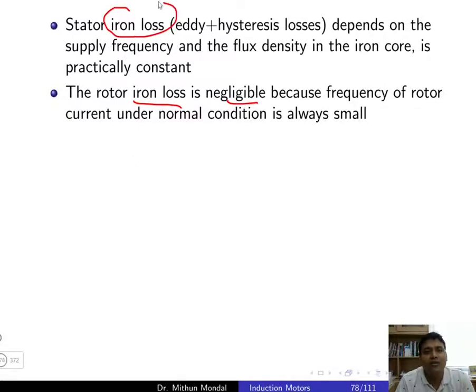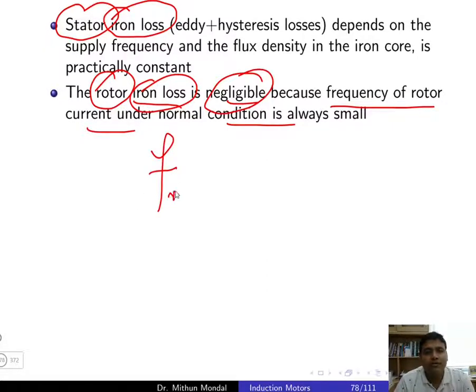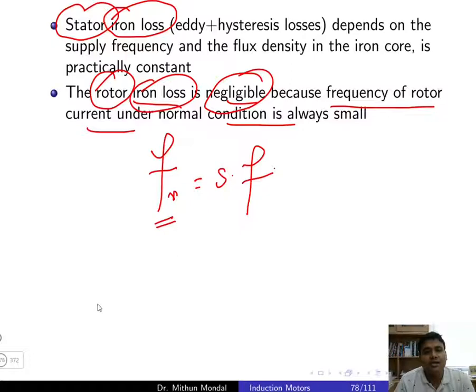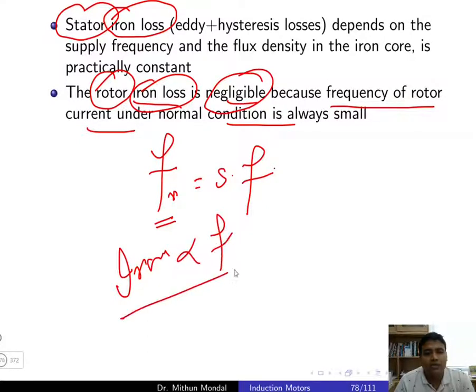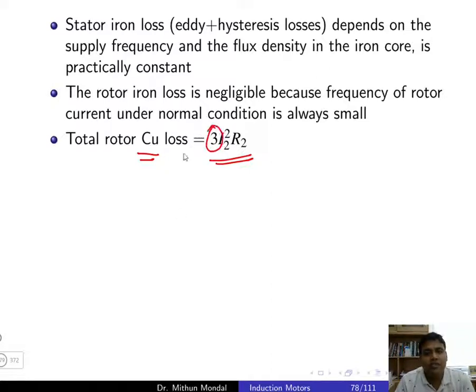When discussing iron loss, we refer only to the stator. The iron loss in the rotor is negligible because the rotor current frequency under normal conditions is very small. The rotor frequency equals slip times the supply frequency, so it is much less than the supply frequency. Since iron loss depends on frequency, rotor iron loss can be neglected. Rotor copper loss is given by 3 × I2² × R2, where R2 is rotor resistance and I2 is rotor current, with factor 3 for a three-phase system.